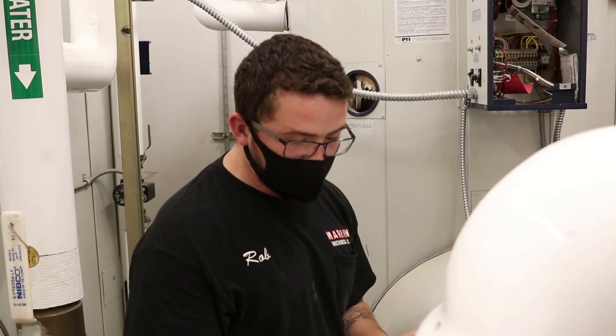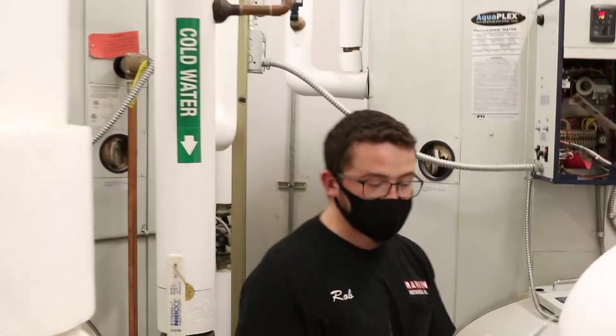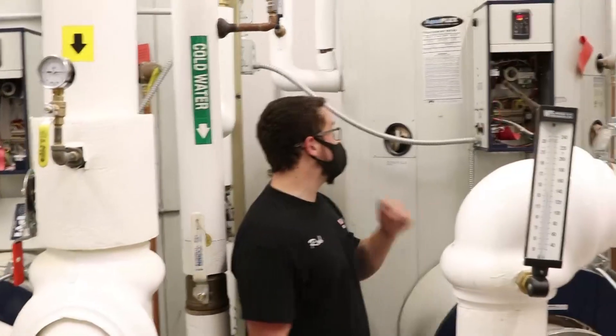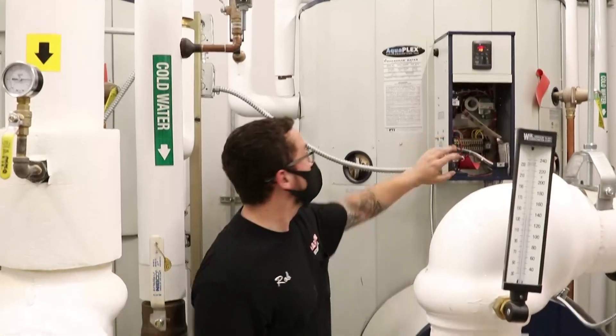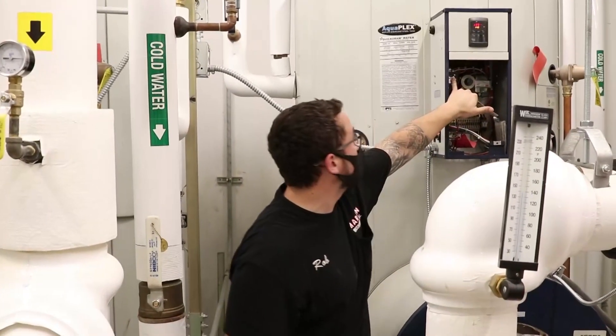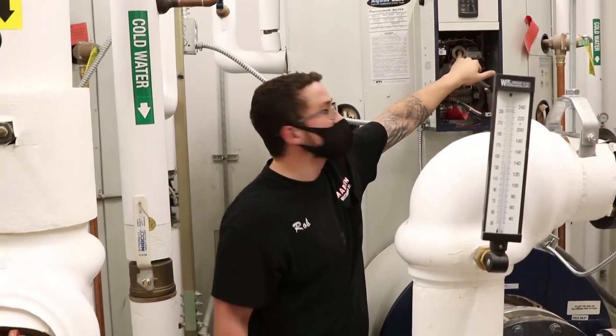So let's talk about maintenance now. Annually, you're going to want to check the safeties like we just discussed. Annually, you're going to want to test the low water cutoff. You're going to want to test the manual reset high limit. You're going to test the upper operating control.